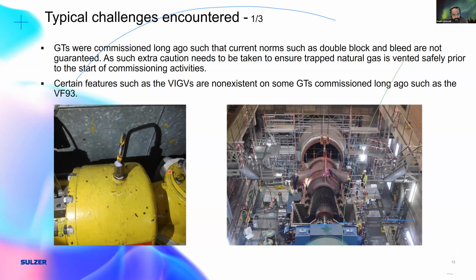This is an example of the setup before the introduction of the double block and bleed norm. If I want to work on this system, I crack open this locking nut, walk away for 15 minutes, come back, and use a gas detector to ensure there's no gas before fully opening this tapping point, which goes to the manometer. Then I can disassemble the ESV and send it off for calibration.